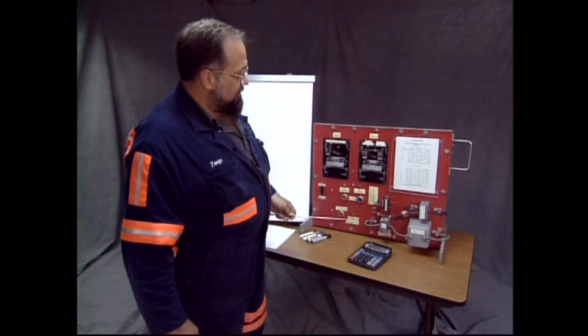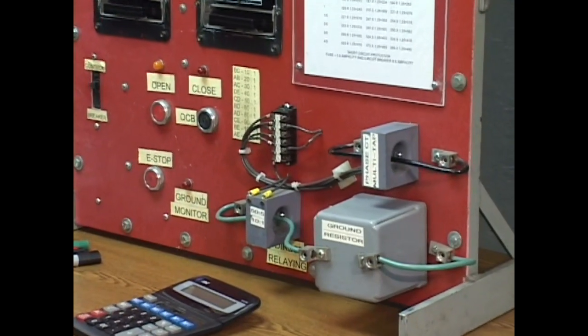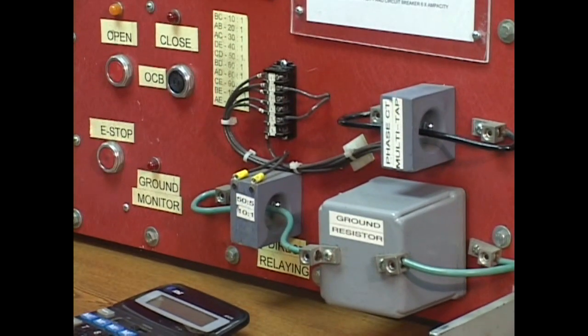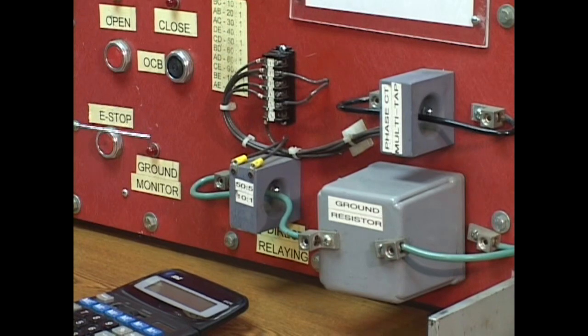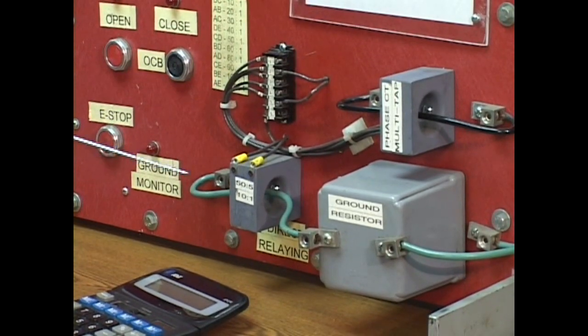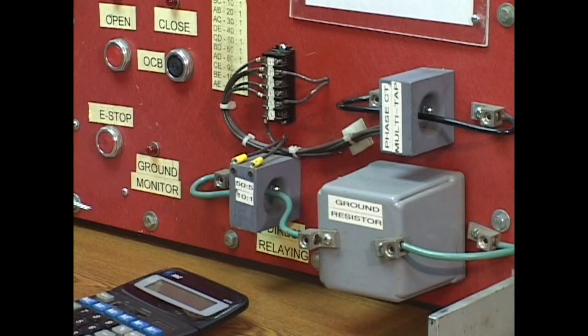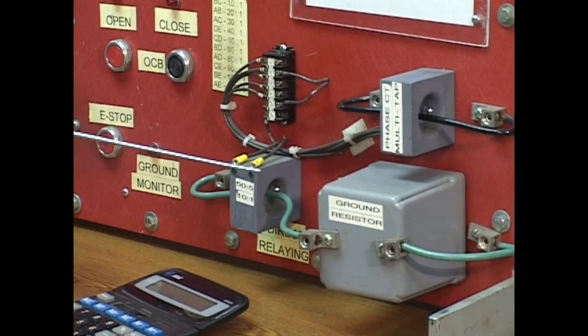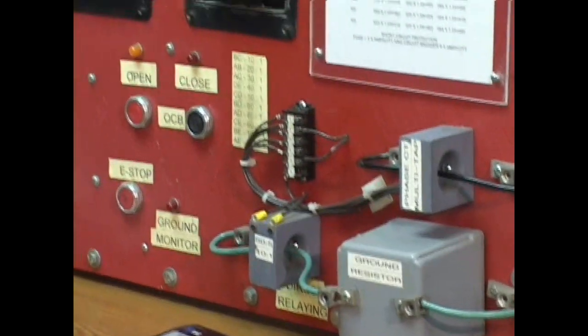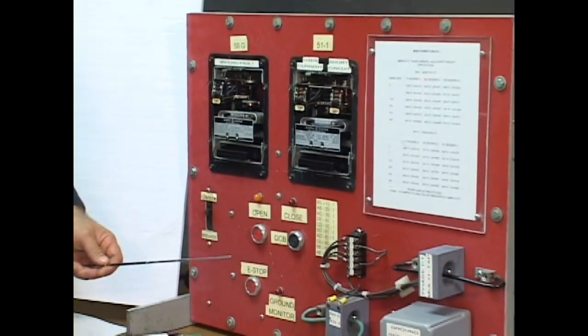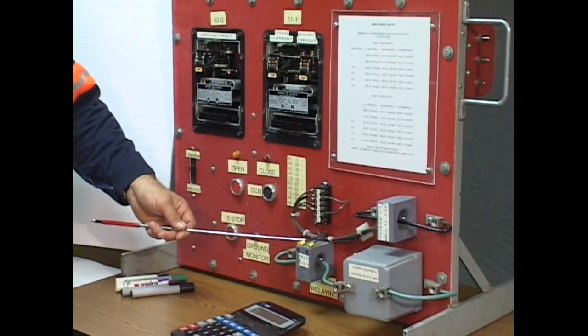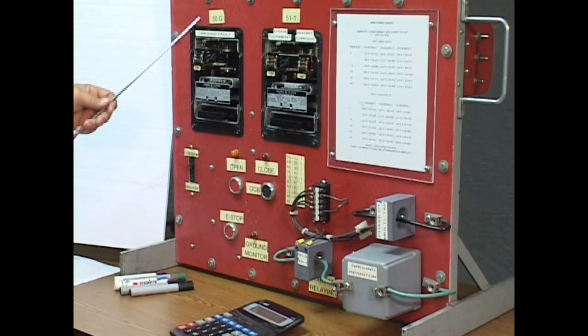The ground fault CT, one ratio. Historically, customarily, it's always, not always, nothing is always, but it's usually a 50-5, 10-1. It's monitoring a ground wire. It reports only to 50G, one CT, one ratio, one relay.